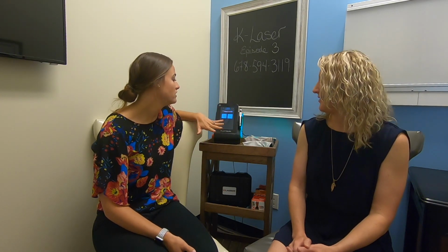You hit the wrist. There's 4 different settings in the wrist one. Each body part has multiple settings. For here we have general, trauma, edema, carpal tunnel. We're just going to do general today. It kind of covers all your bases. It's kind of your safe bet if you're not really sure what's going on. So we go with general, then we choose our body size. Again, we have large, small, average, or a child.